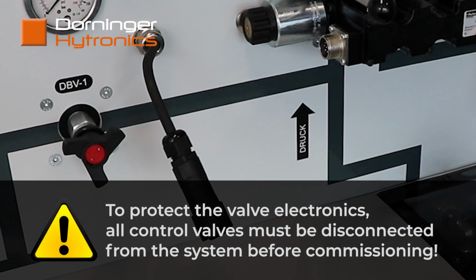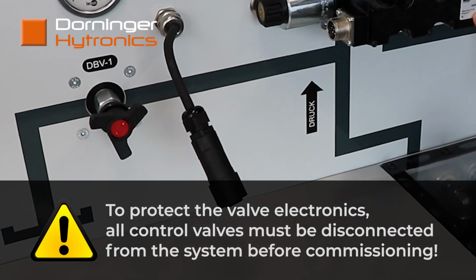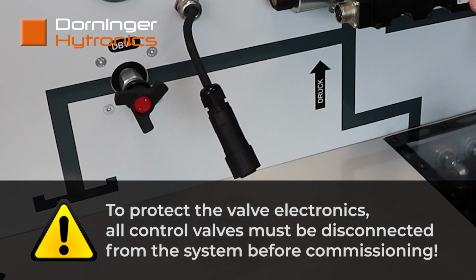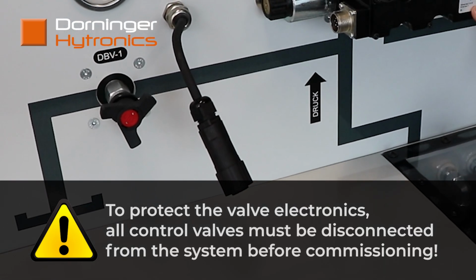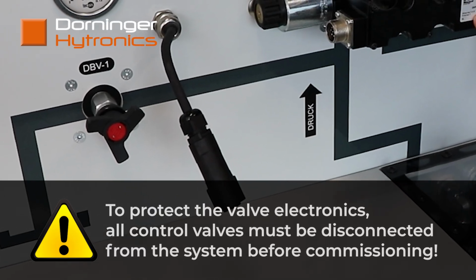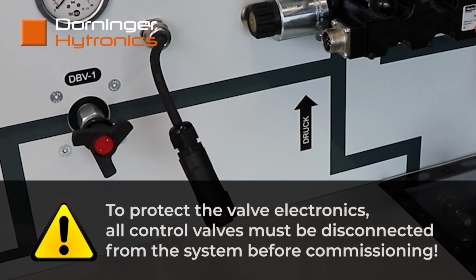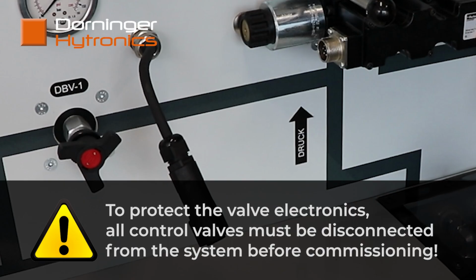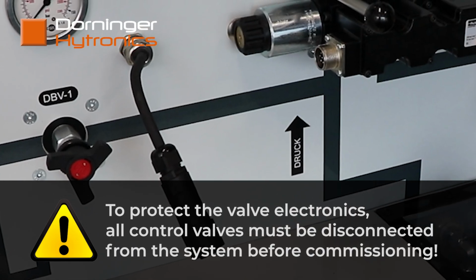As a general rule, the connectors from the machine wiring must not be connected to the control valves before commissioning. This means that, before commissioning begins, all control valves must be disconnected from the machine. Why? If there is a wiring fault in the machine and the main switch is turned on, the valve electronics may be damaged.